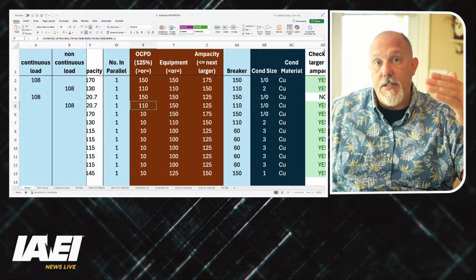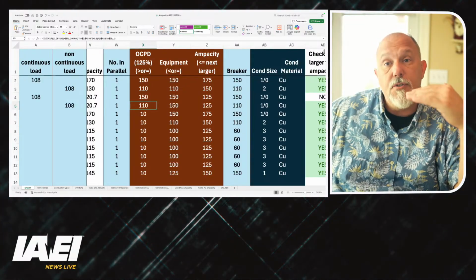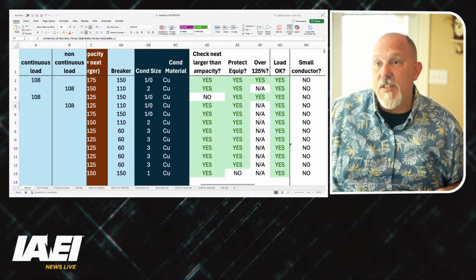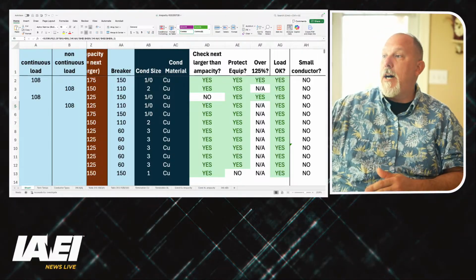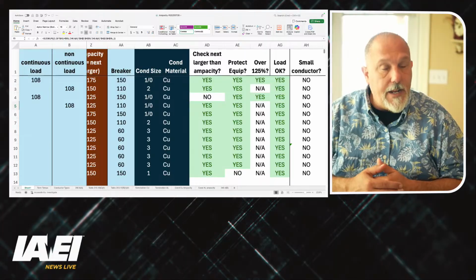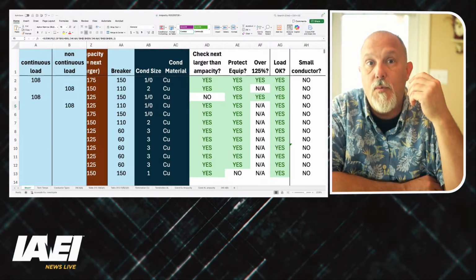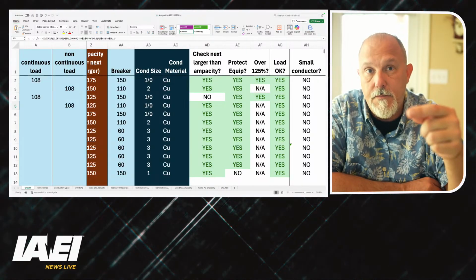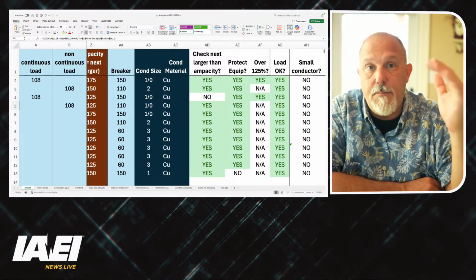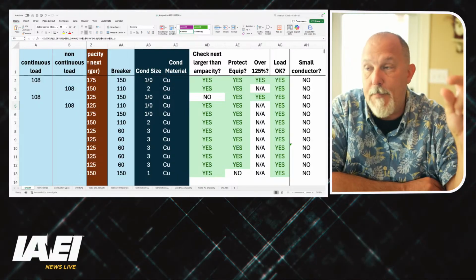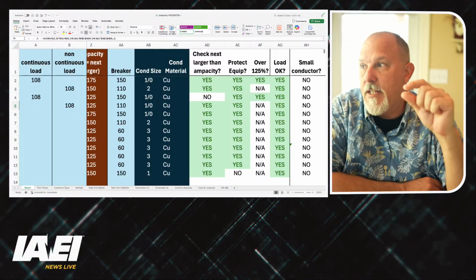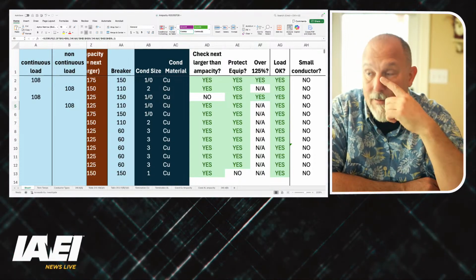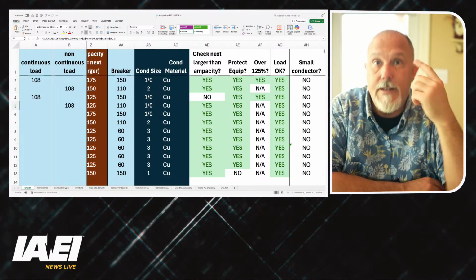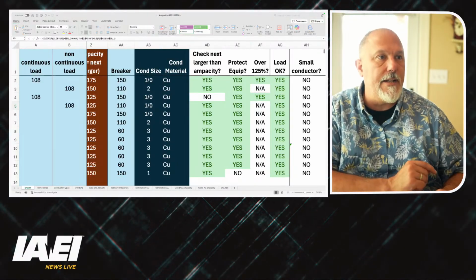I have the same conductor size for both, but for the non-continuous load, I can use a smaller circuit breaker size, which satisfies all of the conditions. So that's the basic difference between 108 amps worth of continuous versus 108 amps worth of non-continuous. The minimum conductor size is still going to be a 1/0 because of our 210 selections, minimum conductor size, and ampacity. But my overcurrent protective device is able to be smaller, exactly 2 sizes smaller. Now let's take a look at the UL standard. Let's take a look at the UL 489 standard while I call this up.